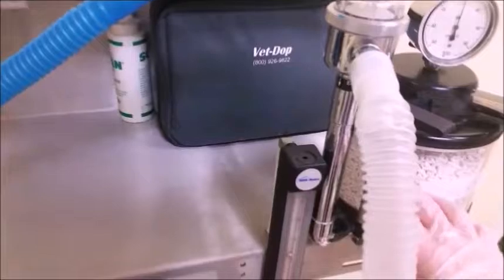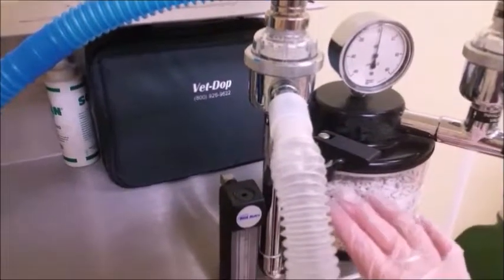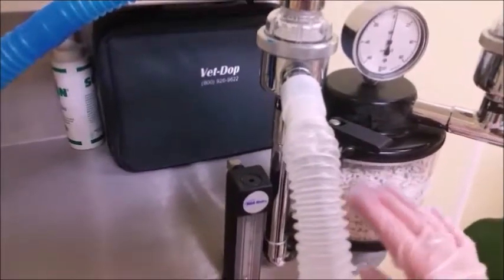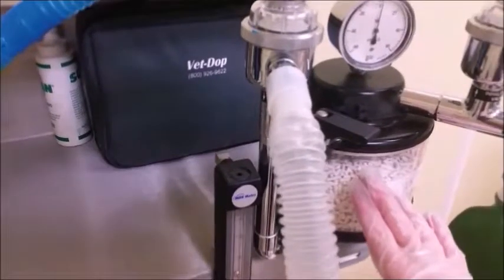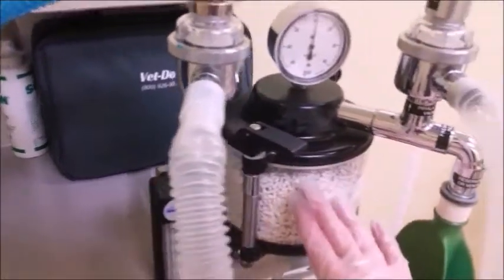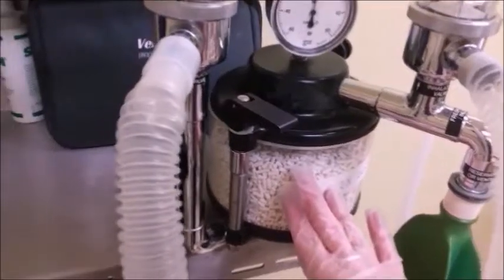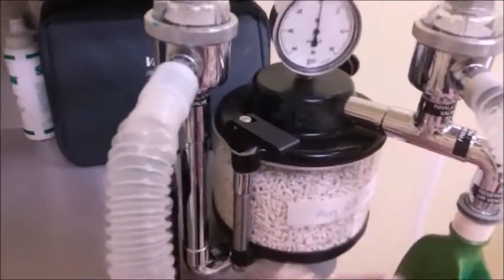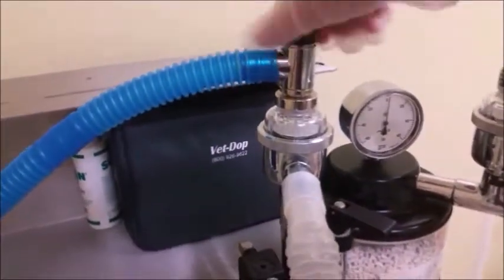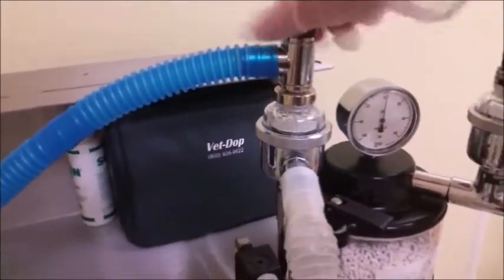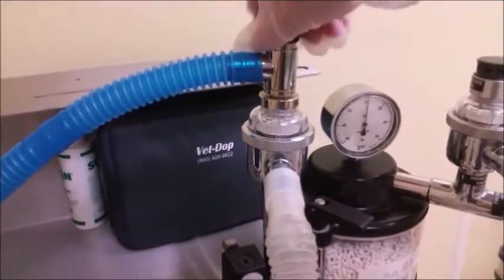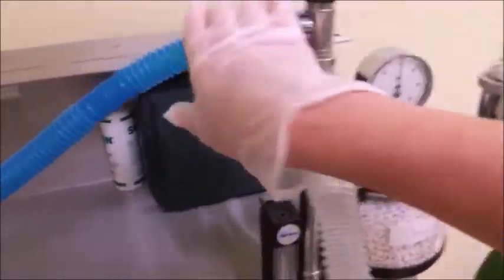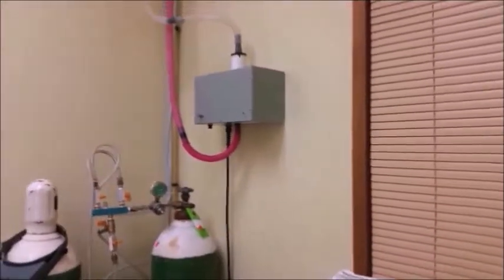Any gases that are moving back through our system are then going to be scrubbed through our CO2 soda lime scrubber. The granules in here will begin to turn purple as the product becomes saturated with CO2 and is at the expiry point. Our pop-off valve does need to be opened back up so that exhalation after manual ventilation can occur, so that gases move through our scavenging unit and are then taken to our scavenger on the wall and then out of the building.